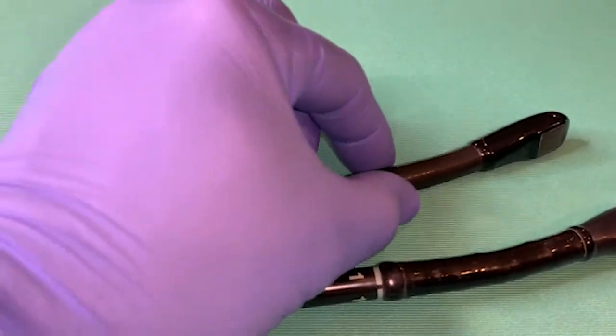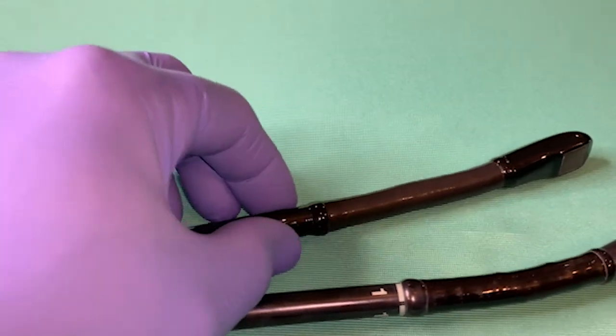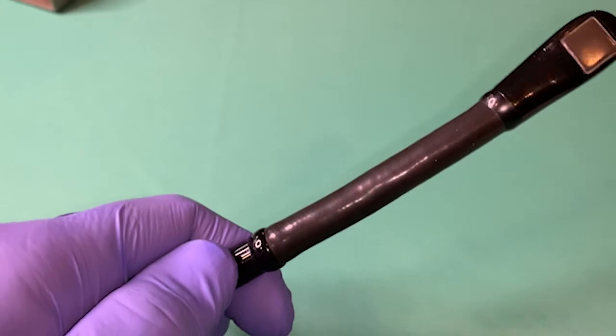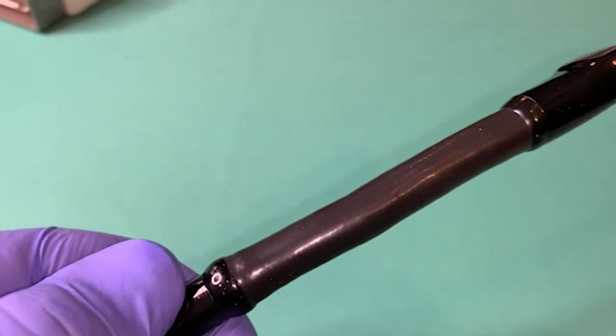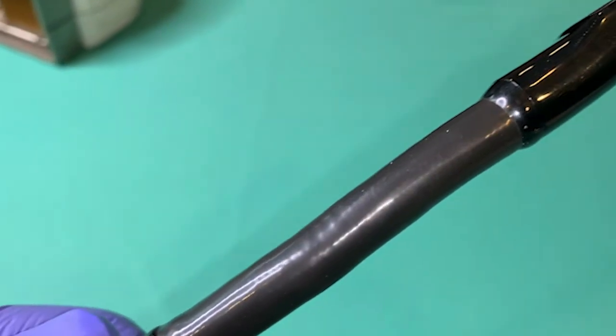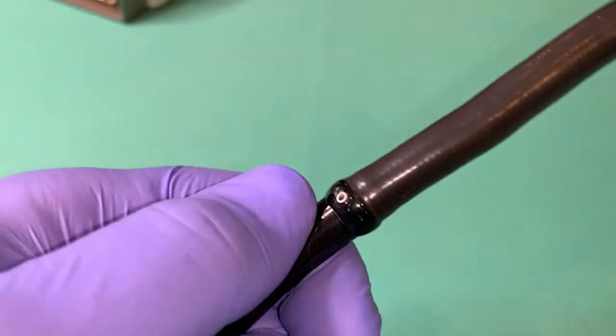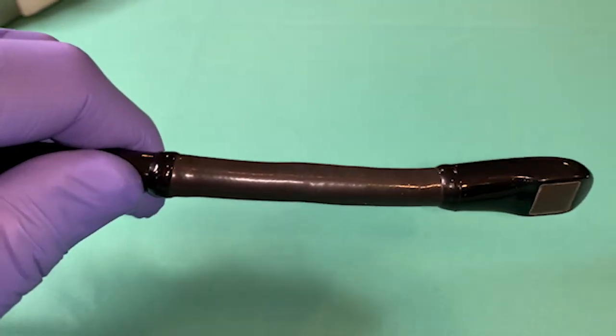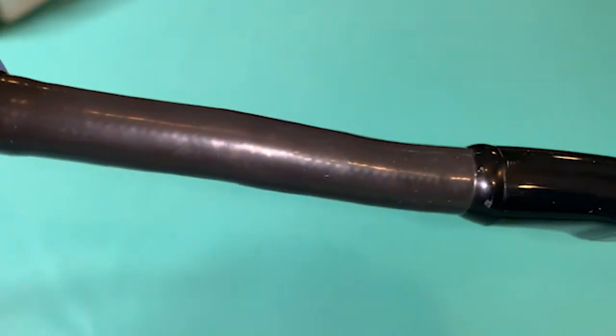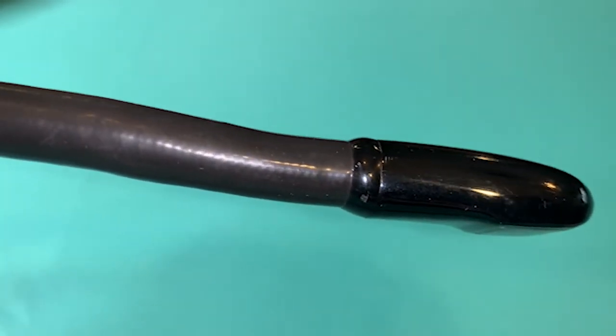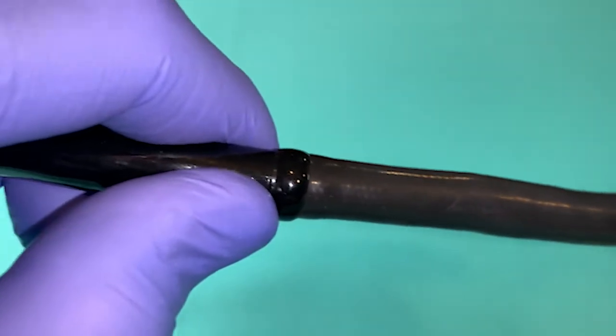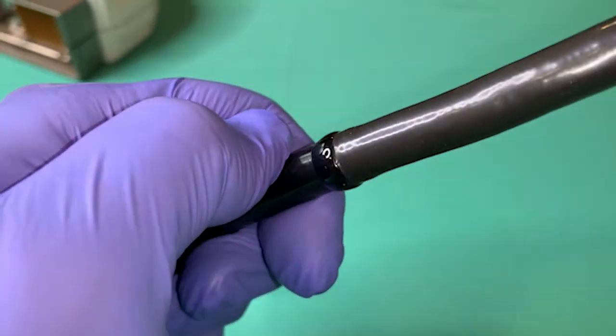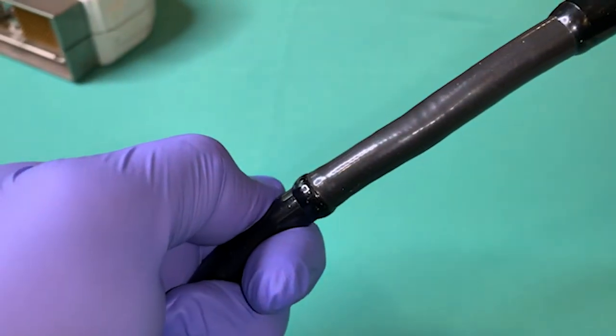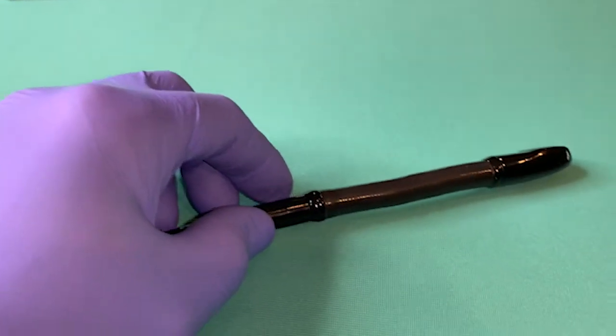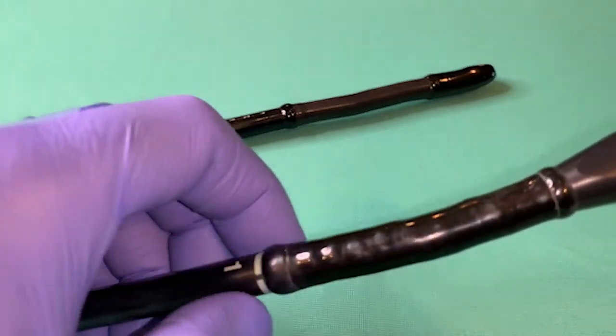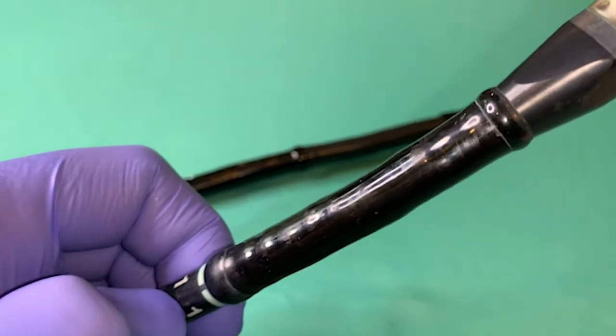The bending rubber is designed to be both flexible and durable. New probes, or those with new bending rubbers, should have a rubber with a very high luster. The luster will fade over time, but its appearance should never appear extremely faded, worn, or pocked. There may be a brown, crusty, or flaky material coating the bending rubber if an enzymatic cleaner is not part of the disinfection process. The bending rubber should appear tight, and on some models you should be able to see some slight definition of the articulation components underneath. Baggy or stretched bending rubbers should be replaced sooner rather than later.